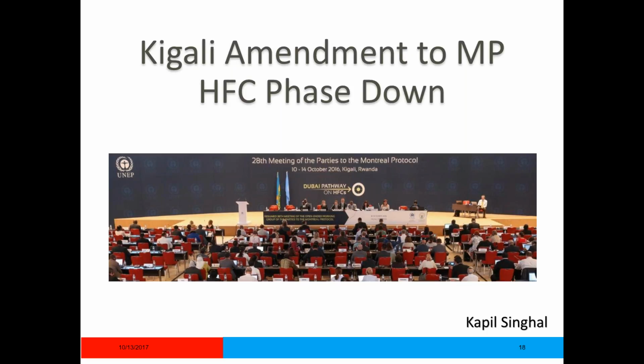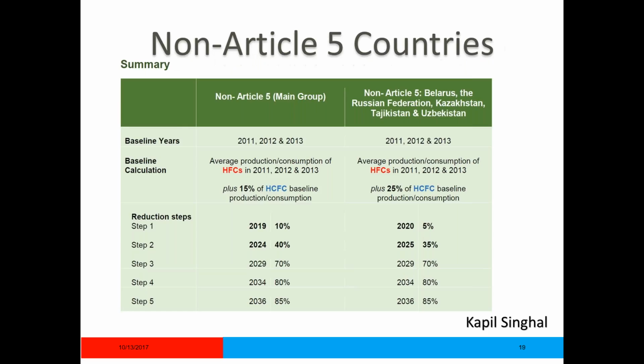Whereas in HFC, we are not talking of zero. We're talking of probably 15% of baseline which will be consumed for essential applications forever. So HFCs are never going to be phased out. A limitation on application and a limitation on volume use will come, but it will not be coming down to zero.